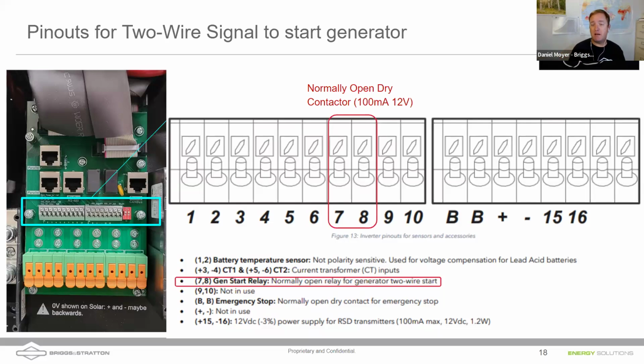There's a lot of other ones here. We cover these more in depth in other talks. Definitely don't use the battery temperature. The CTs, although the CTs are built into the SolArk, it's best practice always to add your CTs. B and B are your emergency stop. And then 15 and 16 are going to be for your rapid shutdown transmitter, for your Tigos, for your APsmart rapid shutdown systems up on the roof as well.